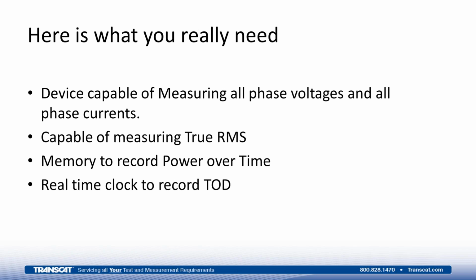Now, one of the important things about this type of measurement is you have to make sure the devices you're using are called true RMS devices. The term RMS means root mean square. It's just a way we express the 120 volts that you might be familiar with. That 120 volt signal actually ramps up to about 170 volts, comes down through zero, goes to minus 170 volts, and comes back to zero. And we somehow call that 120. The way we do that is a calculation called a root mean square on that sinusoidal wave, and we can come up with the 120 volt RMS value.